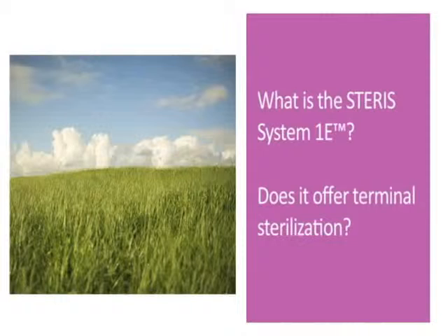The next question is, what is the STERIS System 1E? Does it offer terminal sterilization? The answer is no. The SS1E does not offer terminal sterilization. It is a liquid chemical sterilant processing system. The SS1E can be used to process reusable heat-sensitive devices such as endoscopes and their accessories. However, the SS1E is not a general sterilizer. The sterilant used in the SS1E is a peracetic acid germicide. Because the rinse water is not sterile, devices processed using liquid chemical sterilization cannot be assured to be sterile.